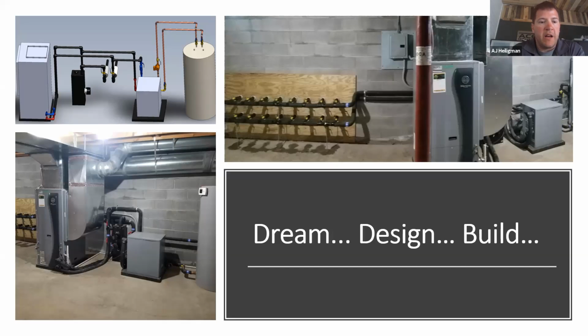If you look in the bottom left photo, between the 2 geothermal units is a black box, and that's a flow center. That's what moves the fluid from the loop field, which is a mixture of antifreeze and water, to each of the geothermal units. If the water to air is calling, it pushes water to that. The water to water call for domestic hot water flows through that unit, each at a different flow rate. These are variable speed pumps, so it tries to save energy running through the loops into each unit respectively, to try to get the greatest temperature difference at the lowest operating cost.